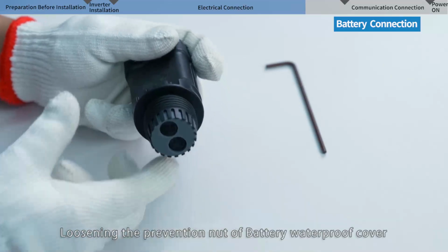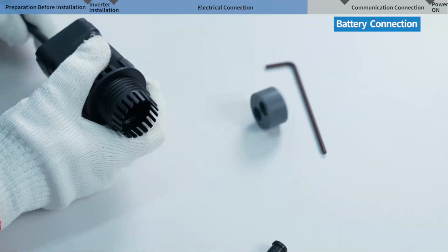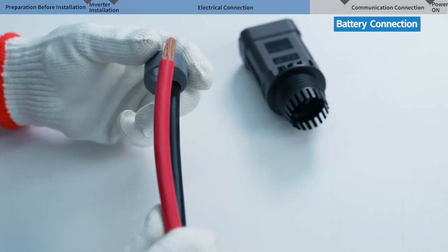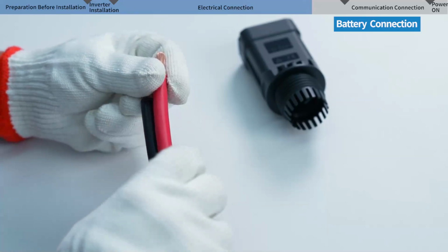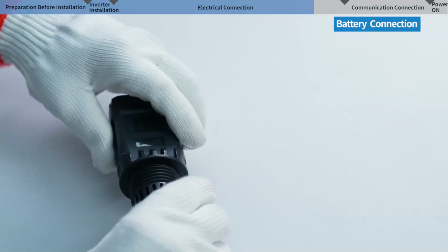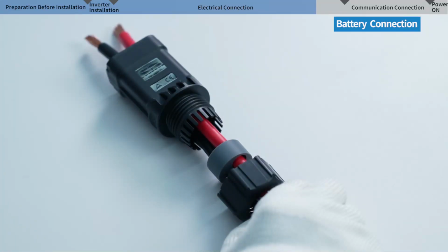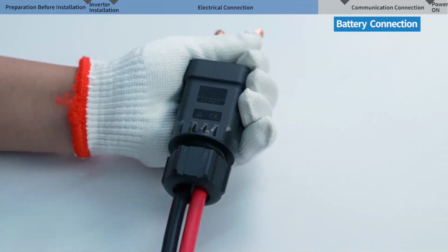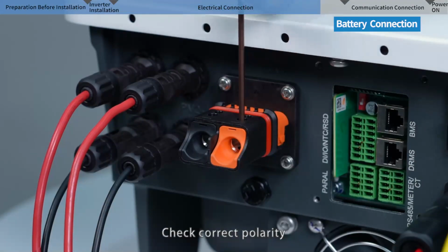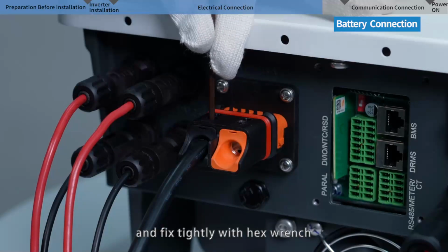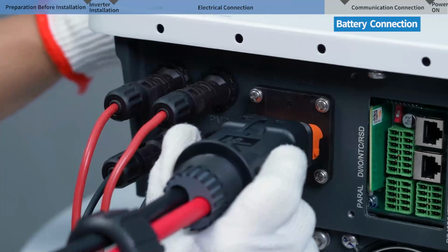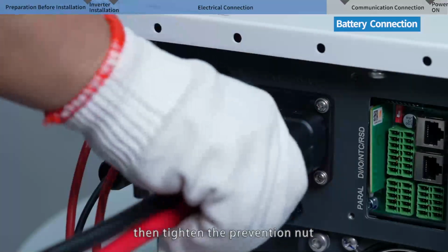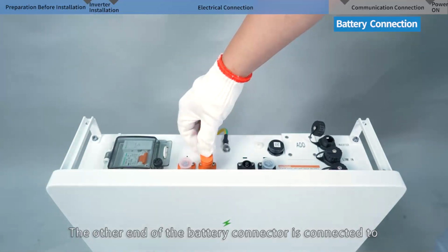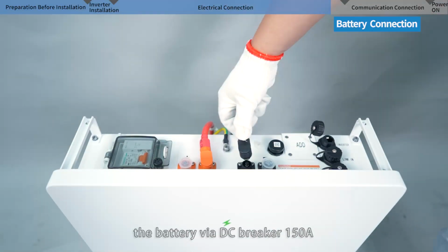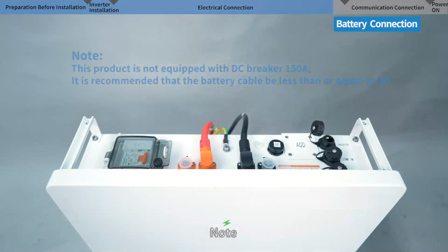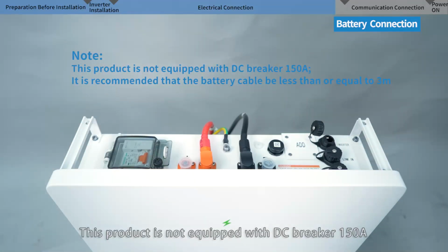Loosening the prevention nut of battery waterproof cover. Thread the cable. Check correct polarity, then install on corresponding terminals and fix tightly with hex wrench. Then tighten the prevention nut. The other end of the battery connector is connected to the battery via DC breaker 150 amps. Note, this product is not equipped with DC breaker 150 amp.